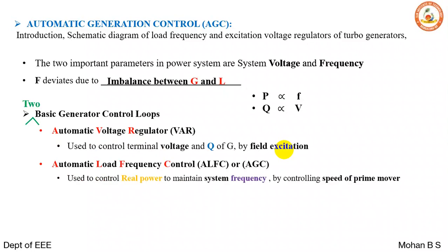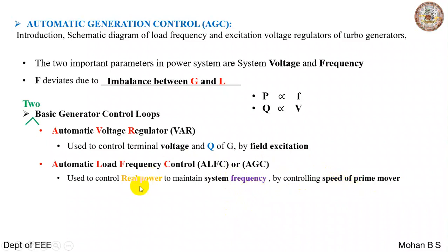The automatic voltage regulators are used to control the terminal voltage and reactive power Q of the generator by controlling the field excitation of the synchronous generator. Automatic generation control and automatic load frequency controls are used to control real power to maintain system frequency by controlling the speed of the prime mover.